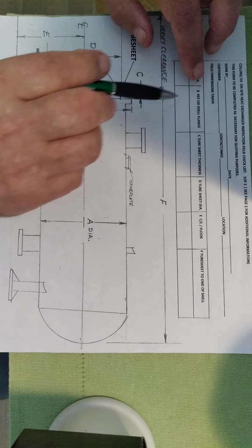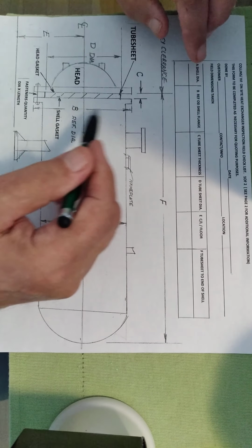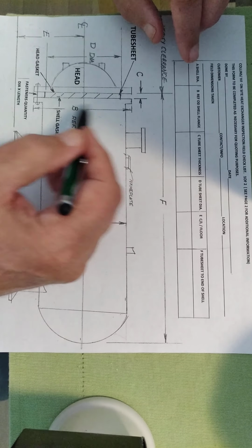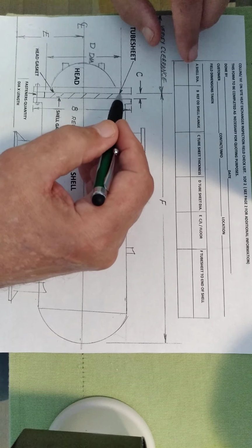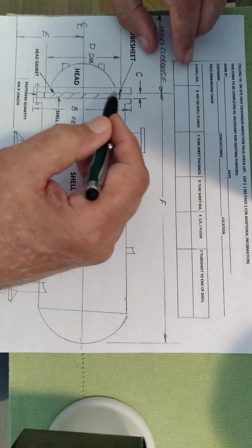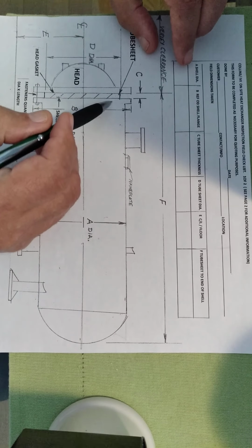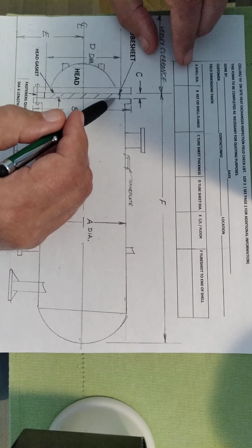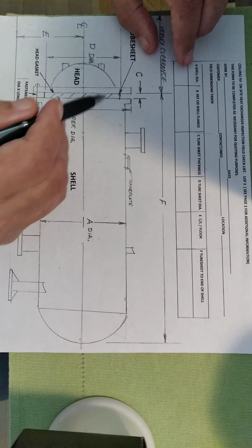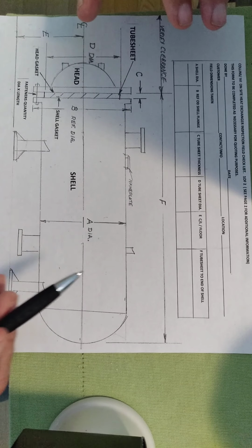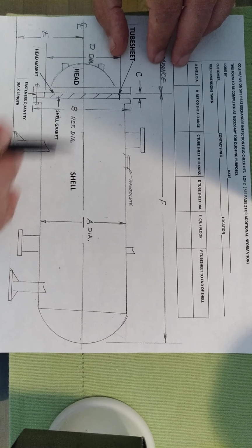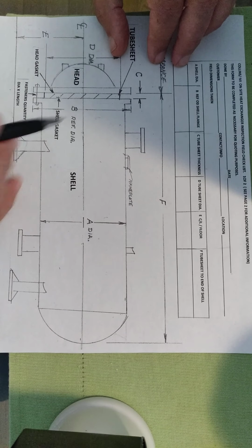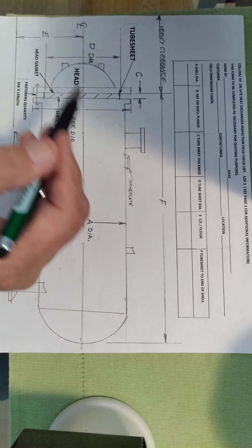Get that. The B reference is a good dimension to get, as you'll see in a later course that we have, because you're going to want to have the tube sheet diameter if you can get it. Why do we need that? Between the shell diameter and the tube sheet diameter, it gives us an idea of the most tubes, based on their diameter, that we could even consider mathematically getting inside this shell or this unit. So these dimensions help us to figure that.